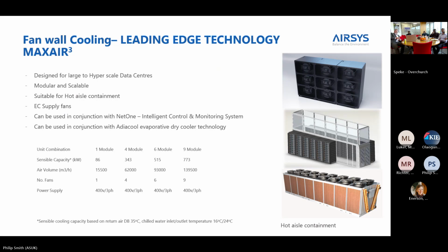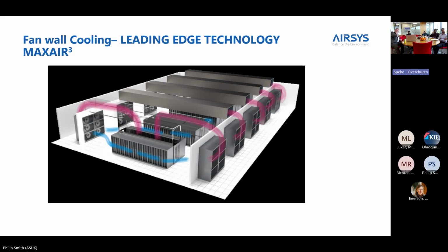Well, if you're a hyperscaler, you'll be using fan wall technology, which is basically, if you imagine the old kids' toys of Stickle Bricks, and each brick is a fan, a coil, and a filter, and you just combine them together and make them as many as you want. We do them in configurations typically up to 9, which can be up to 900 kilowatts of heat rejection, or cooling, should I say. They're installed into the hot aisle. So your hot aisle enclosed environment. There's no refrigerant. They're connected then to dry coolers on the roof, which may or may not be adiabatically cooled, which is another factor these days for your WE to be considered, but there's no refrigerant in them. So in terms of free cooling, once these start running at higher elevated temperatures, you can apply free cooling by the means that you reject that heat.